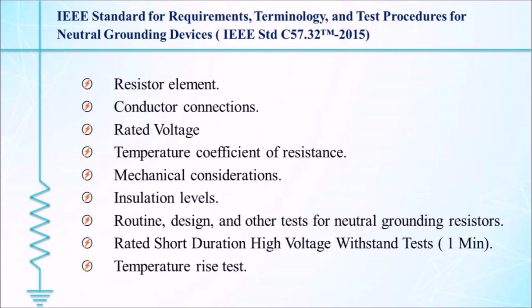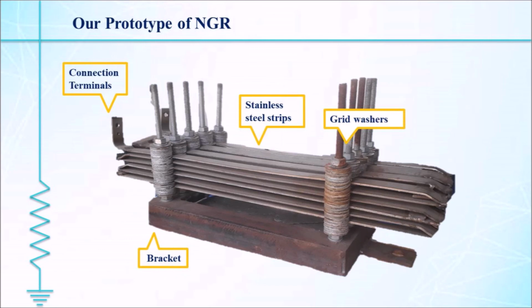This test shall be made by passing a rated current through the resistor unit until the temperature rise becomes constant, and determining the hotspot temperature rise. The temperature rise test shall be made in a room that is essentially free from drafts. This is the prototype of NGR which we have made.